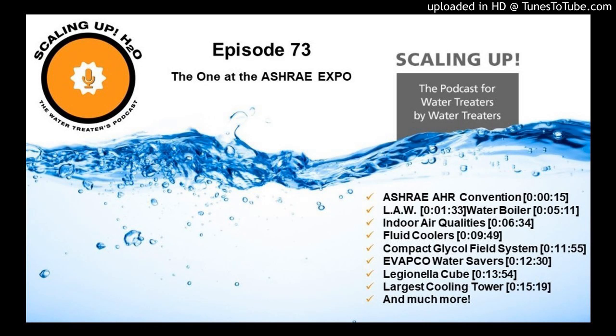But it doesn't do very well at dry cooling in the winter. So if the objective is to shut off the water in the winter and not have to maintain a basin heater to maintain the water temperature in the basin and worry about freeze prevention and that kind of thing, then we go with a product that's all coil. The DT fluid cooler is a bare tube coil as well, so it has more dry capability than the hybrid. The variation we've just introduced to the market is the fin tube coil version of the DT product.